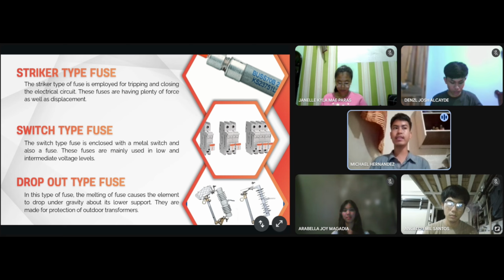It's designed with a handle or lever which makes it easy and safe to operate, especially when maintenance or replacement is required. Inside, the fuse element works just like in other types of fuses. When too much current flows through, it melts and breaks the circuit to prevent damage. What makes the switch type fuse stand out is that it allows you to disconnect the circuit manually before working on it, providing an excellent layer of safety for electricians and technicians.